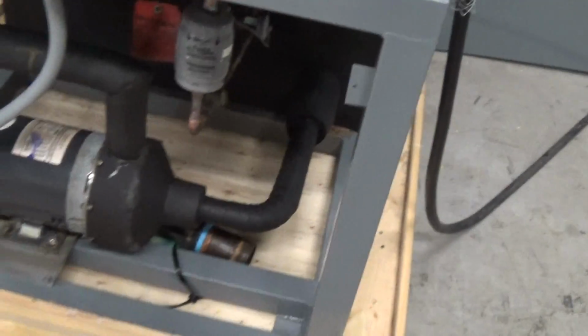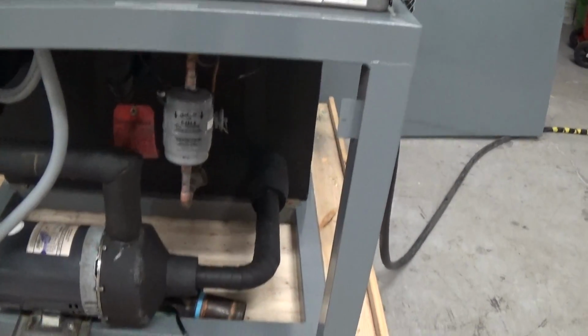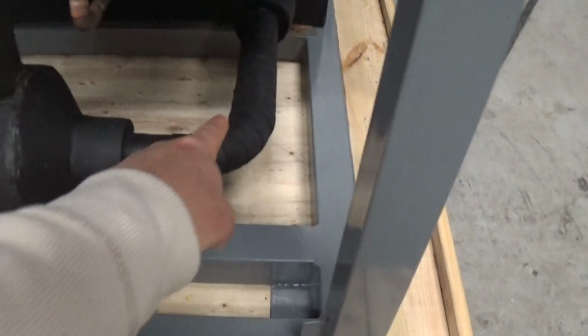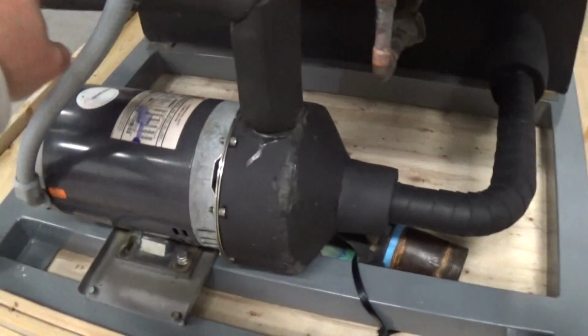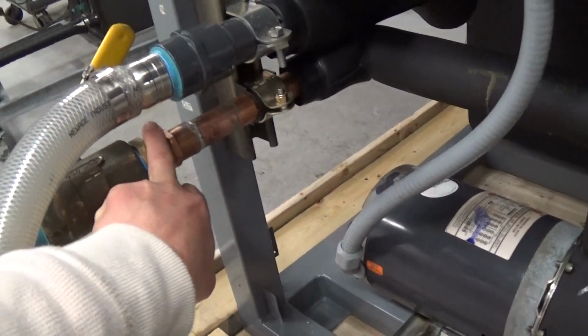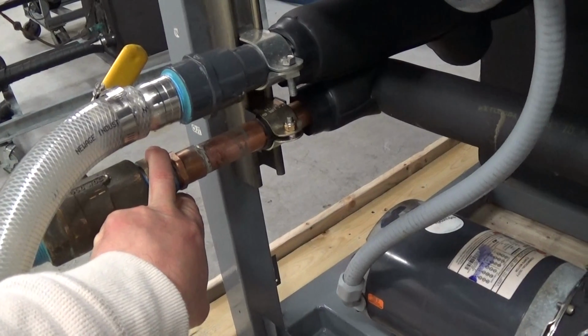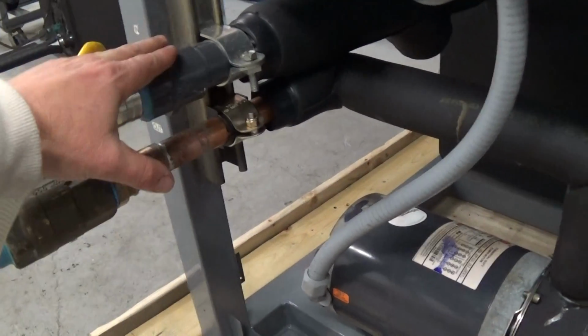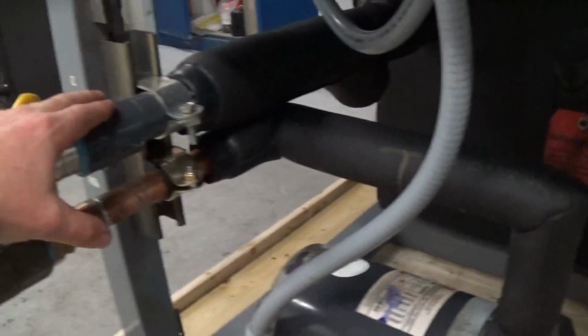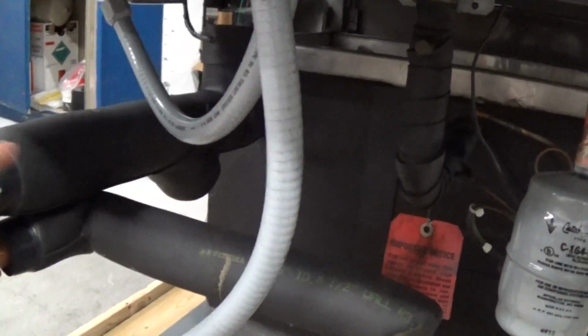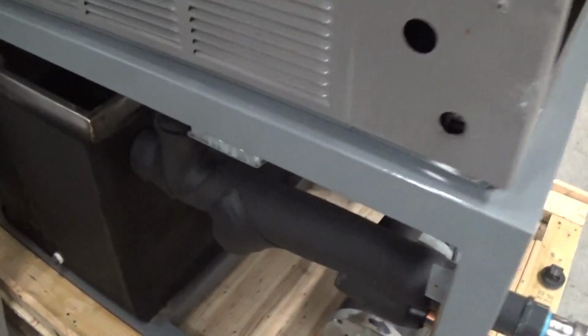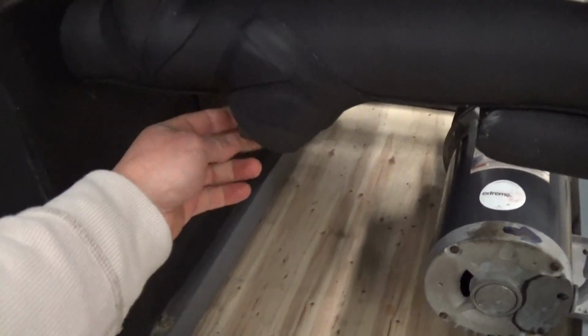So this has this 1.5 horsepower process pump. It draws off that tank here and comes up and comes out. So your lower fitting here is out to process. Your upper fitting is the return, and that return comes back into the tank here where the refrigerant to fluid heat exchanger is. This here is a Y strainer.